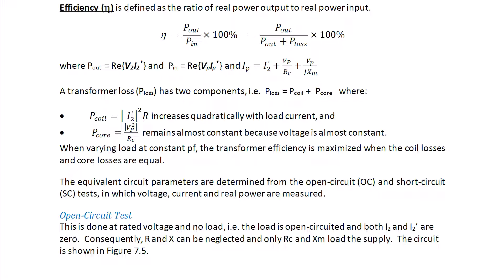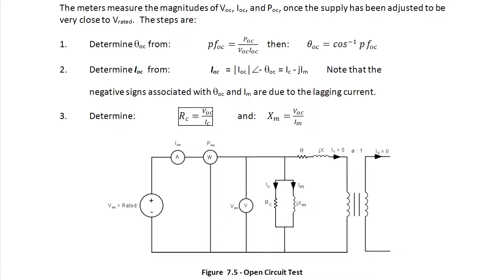The open circuit test is done at the rated voltage and no load, i.e., the load is open-circuited and both I2 and I2 prime are zero. Consequently, R and X can be neglected and only RC and XM load the supply, as in the circuits shown in Figure 7.5. In this circuit, the meters measure the magnitudes of VOC and IOC and POC, and once the supply has been adjusted to be very close to V-rated, we use the following steps to determine RC and XM.